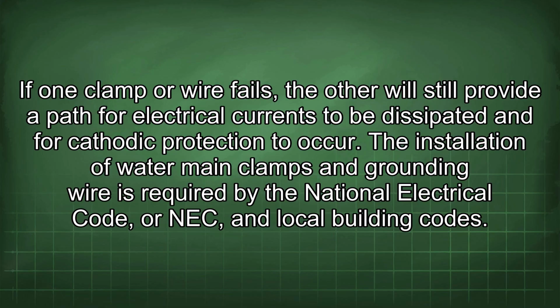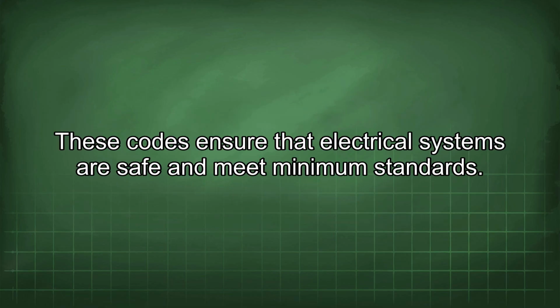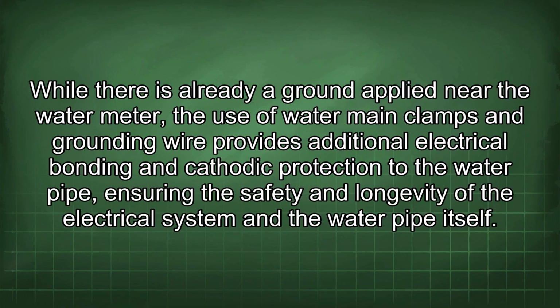The installation of water main clamps and grounding wire is required by the National Electrical Code, or NEC, and local building codes. These codes ensure that electrical systems are safe and meet minimum standards. While there is already a ground applied near the water meter, the use of water main clamps and grounding wire provides additional electrical bonding and cathodic protection to the water pipe, ensuring the safety and longevity of the electrical system and the water pipe itself.